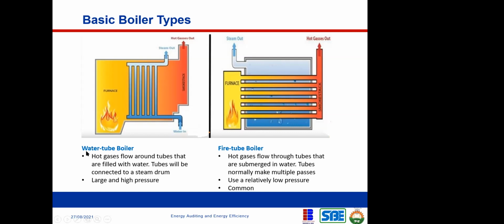Okay, so now this is the water tube boiler. If you notice, water is actually passing through the tube. Why? This is your furnace, where you're heating. This is your burner, right? Heat is being generated here, but you need to transfer the heat into a carrier. In this case, water is our carrier here. So water passes through the tube and absorbs the heat.